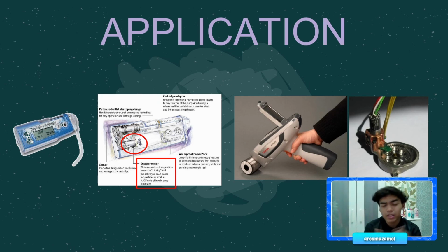In such a device, a motor is usually used to rotate or position a piston that controls the injection of the drug. The motor operates infrequently, time on or time off. It must hold the position with no current and move the piston at a very steady speed. Together with the requirement for simple and compact electronics, the stepper motor truly makes sense.